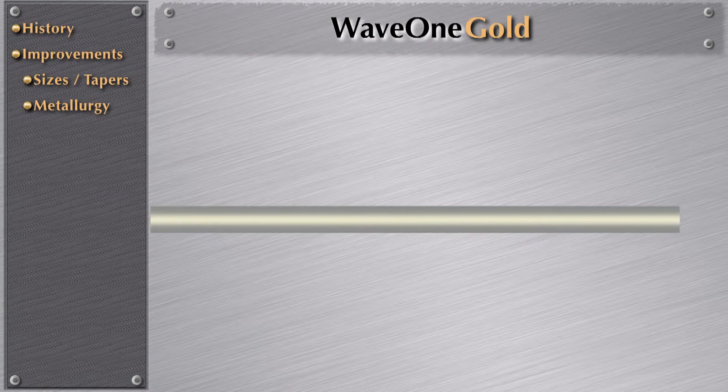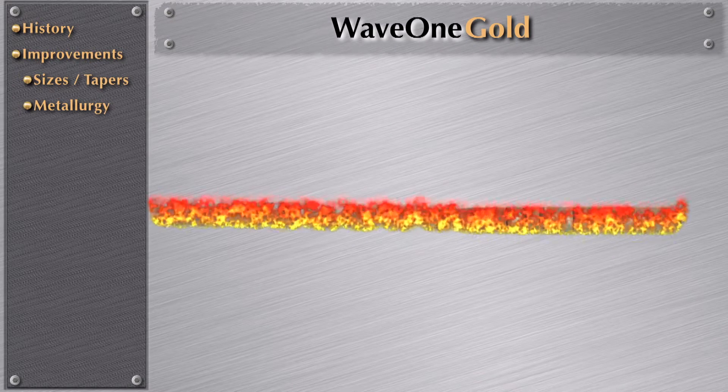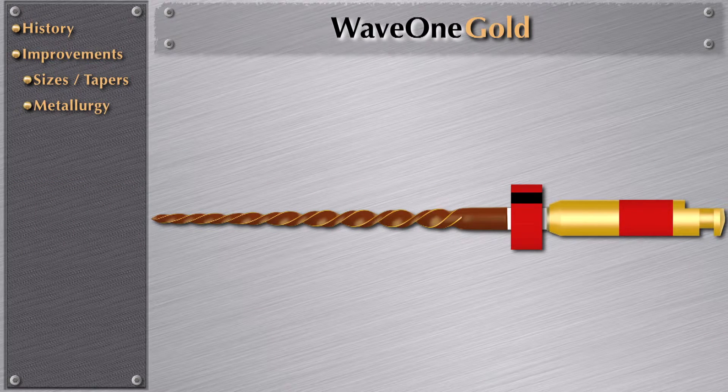With WaveOne Gold, this is one of the most important changes applied to this instrument. When regular nickel titanium is made, they cut these rods, then the instrument is ground, and after grinding it goes through a heat process. This heat process gives the instrument the gold color. Then the rubber stop is placed, then the handle. This is one of the biggest improvements in WaveOne Gold, because it gives tremendous properties in cyclic fatigue, torsional strength, flexibility, and bending, as we will discuss later on.